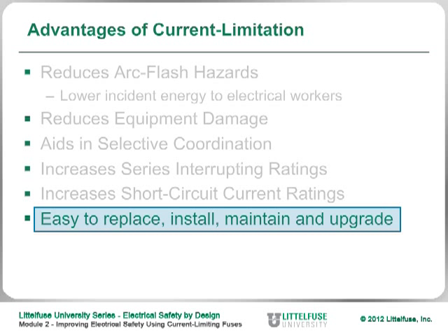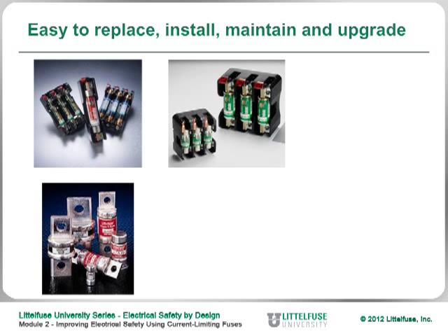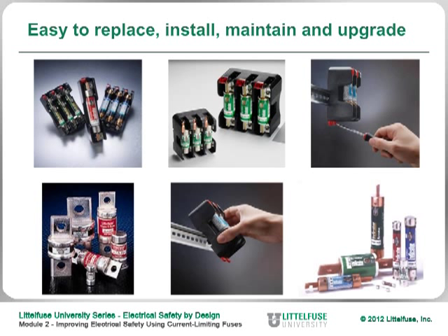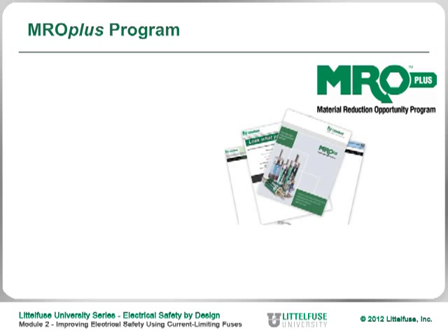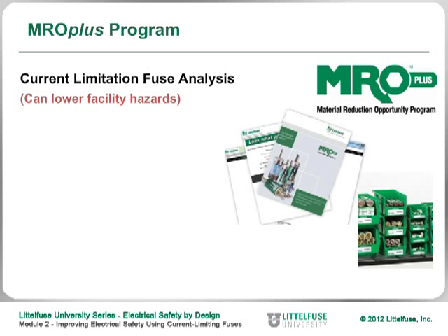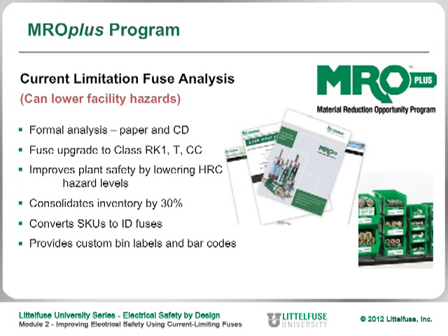Other advantages of current limitation are that fuses are easy to replace, install, maintain, and upgrade. They fit in standard rejection-type fuse clips. Class J fuses and Class T fuses take up less space than standard fuses. Littelfuse has an MRO Plus program that, for users with many fuses in their facility or designing a new system, helps select the proper current limiting fuse with the most current limiting capability while still having time delay built in — so fuses won't open on motor startup inrush or transformer inrush.